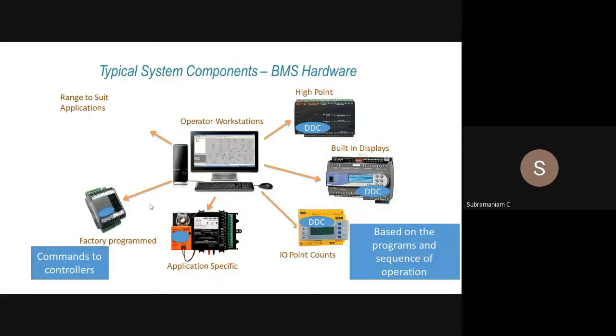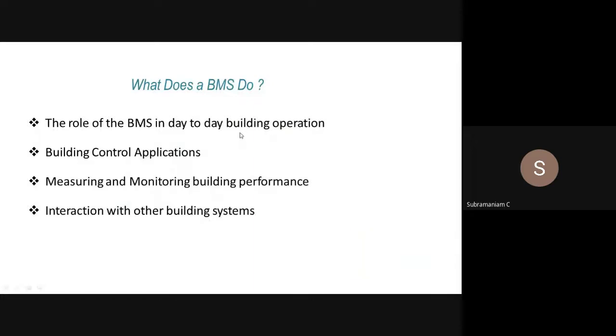It takes a lot of time to change those minimum maximum CFM settings. So that is what the designer is supposed to give in the schedule itself: what the minimum and maximum CFM settings are. Then the factory person will set it and send it. Then we have IO point counts and DDC controllers. All this will be the BMS hardware components. So we saw what this is.